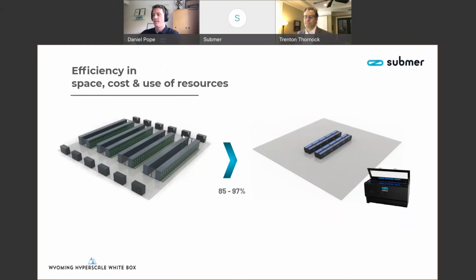During your design process, has this level of density been validated? Is it what you're speccing to, Trenton? Yeah, so we're speccing to 80 kW per pod. We know it can go up to 100, but the actual content of the pods will vary a bit, so we're working to an average density of 80 kW. We know some pods that are just full of straight compute will be at 100.